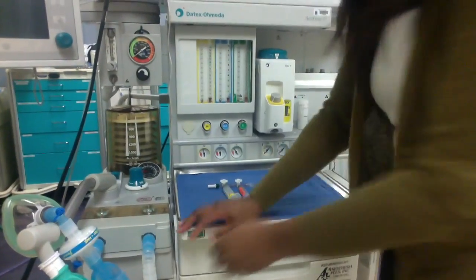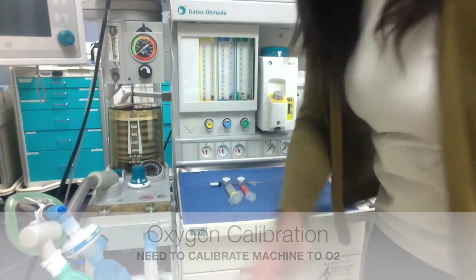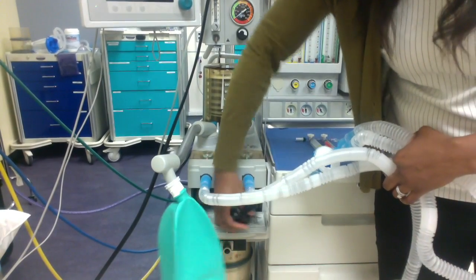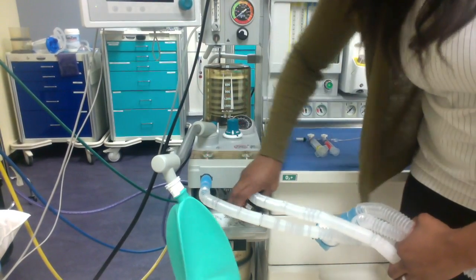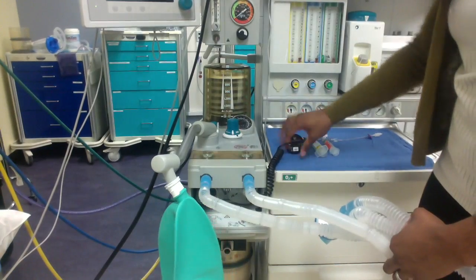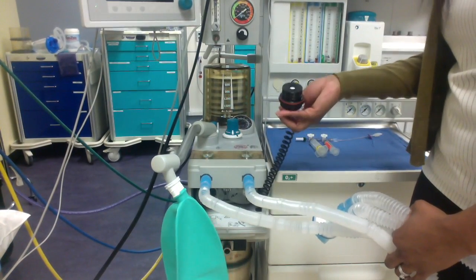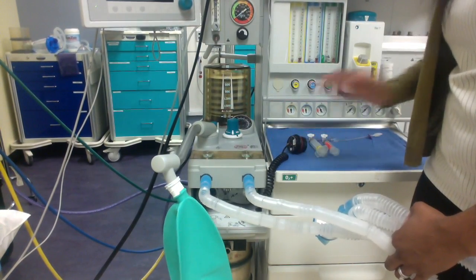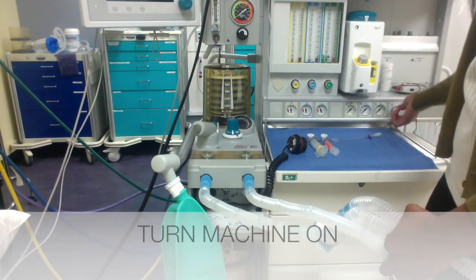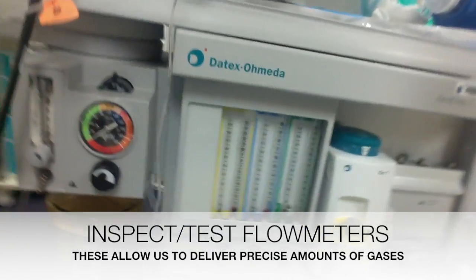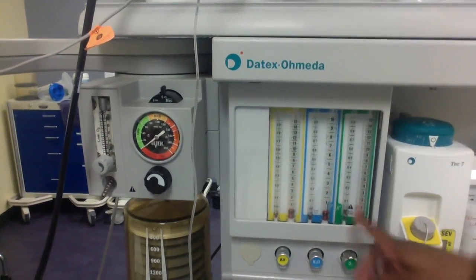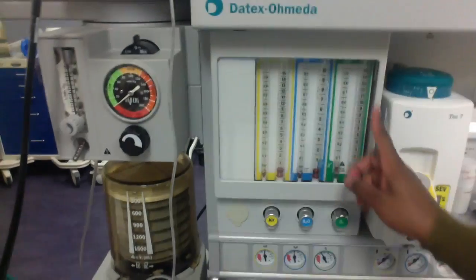Next step is to open up my calibration system. In there's a cap that I can flip open. This is the O2 calibration system. I want this to regulate and calibrate to room air. So I have it seated here without touching it, and then I can flip my machine on. My machine is booting up. I can check my flow meters. This is air, nitrous, and O2. And these are called Thorpe tubes.